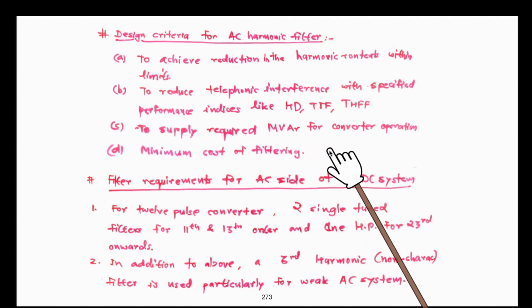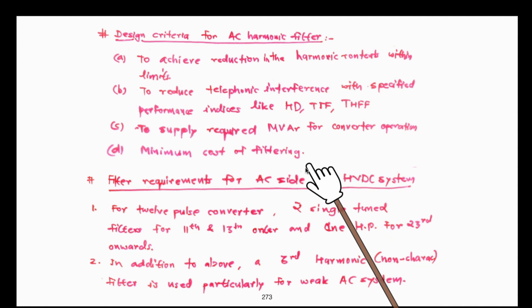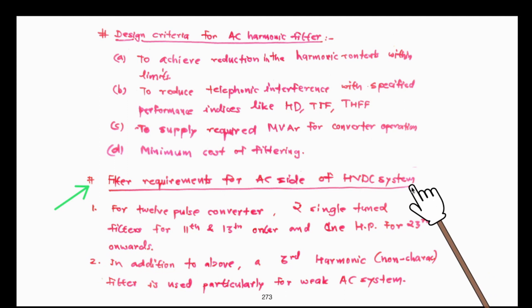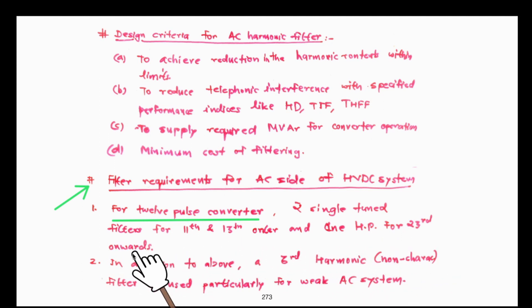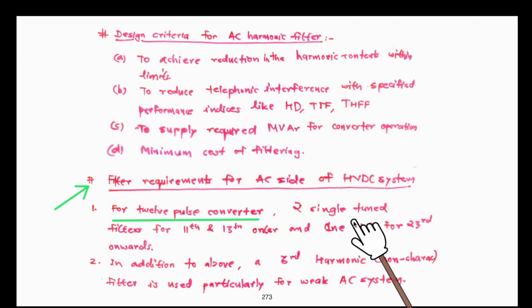Having established the criteria for filter design, we must now determine how many filters are to be designed in order to effectively minimize harmonics. The filter requirements on the AC side of an HVDC system for 12-pulse converter operation: it is recommended that two single-tuned filters for the 11th and 13th order harmonics and one high-pass filter for 23rd harmonics onwards be used to eliminate all harmonics in the AC current.